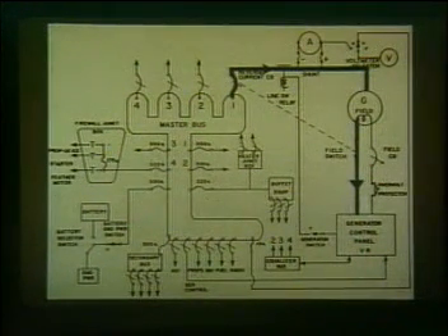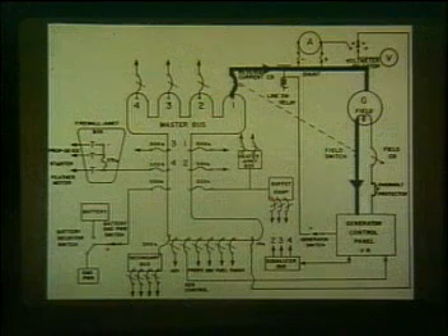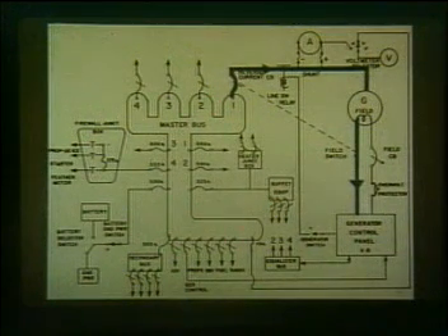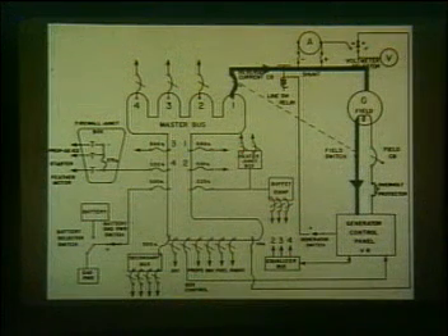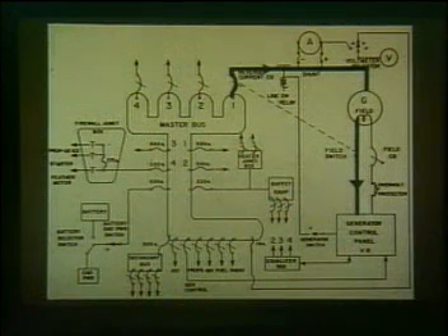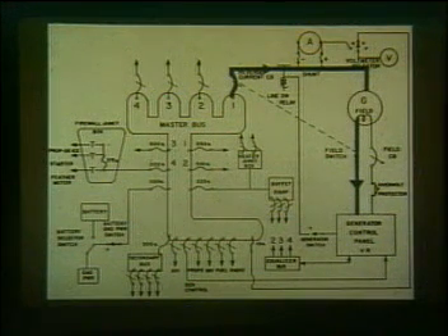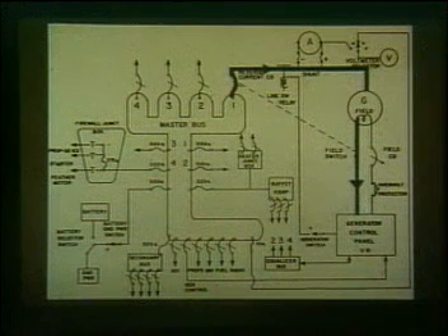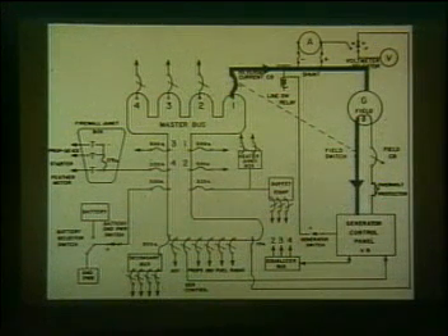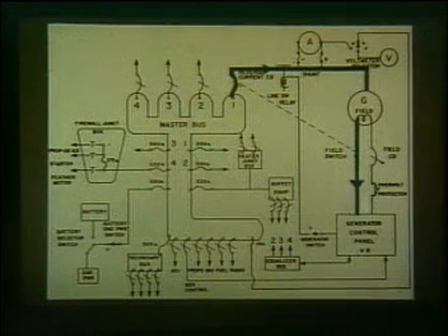When the generator output voltage drops due to insufficient engine RPM, a reverse current flows from the master bus through the generator and to the generator control panel. This small reverse current flow through the generator control panel will cause an interruption of power to the line switch relay through the generator switch, causing the line switch relay to de-energize and remove the generator from the bus.